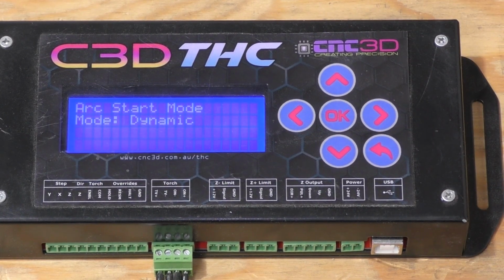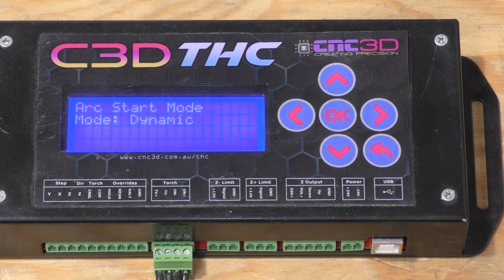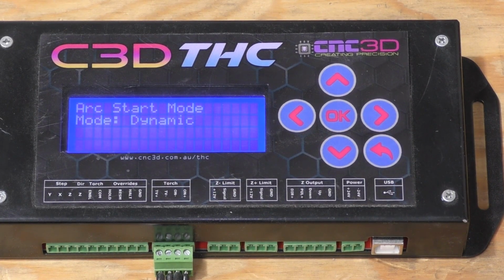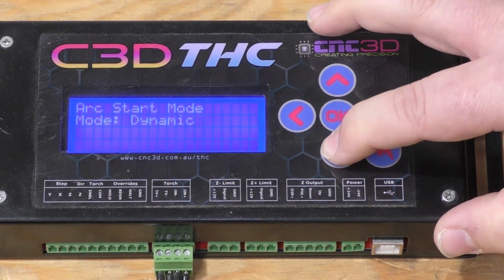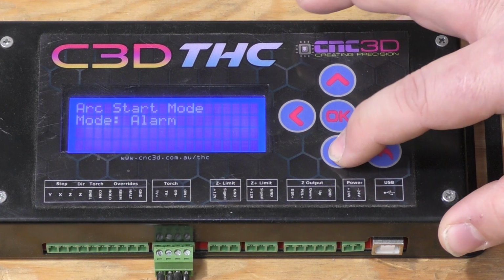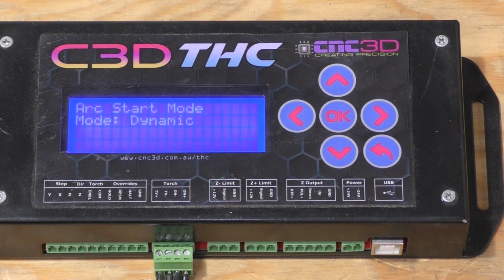Next one down is arc start mode. This is where you can change how the THC reacts when the arc is first ignited. We've got a few options here. For arc start mode, we've got dynamic, we've got none, and we've got alarm. Dynamic will be the default mode when you first receive your controller. What dynamic does is, when the arc first ignites, it will look for that arc OK signal. If your plasma cutter doesn't put out an arc OK signal, you won't be able to use the dynamic mode.